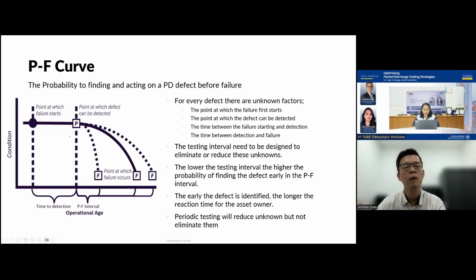So what do we need to know? A lot of times when we start PD surveys or engage people to do them, it's always on an annual basis. They think once a year is enough, so this year no PD, maybe next year they get a contractor to detect. But if you only do it annually, there's a high chance you'll miss the point where failure starts and where the defect can be detected, and you'll only catch it at the final or late stage.